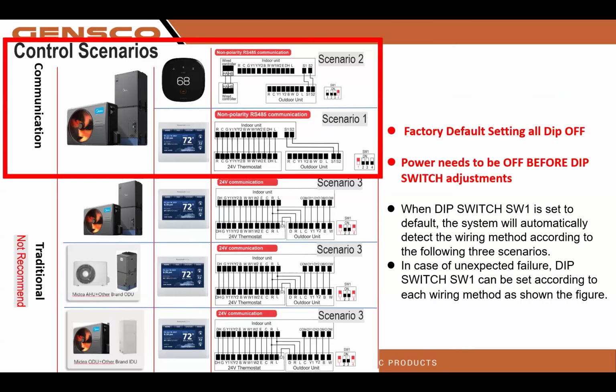Dip switch settings, control scenarios. S1, S2, 2 wires to the outdoor unit, HAHB to HAHB on the indoor wired controller, the TL04 stat, and you do not have to set any dip switches, but we can set a dip switch to auto recognize. Scenario 3, 24-volt communication. Guys, this is no different than anything you've already installed. We've been installing 24-volt controls for 55, 60 years now. We've got RC, G, W, Y, O. Our reversing valve is energized in the heat position, not the cooling position. I highly recommend that you use fully communicating.